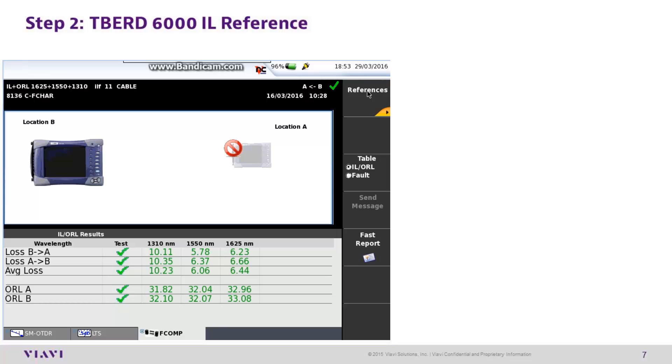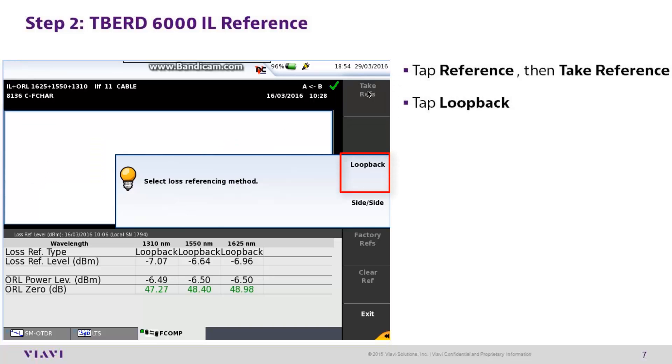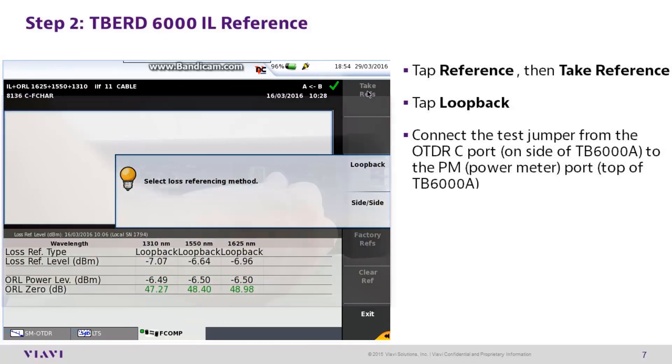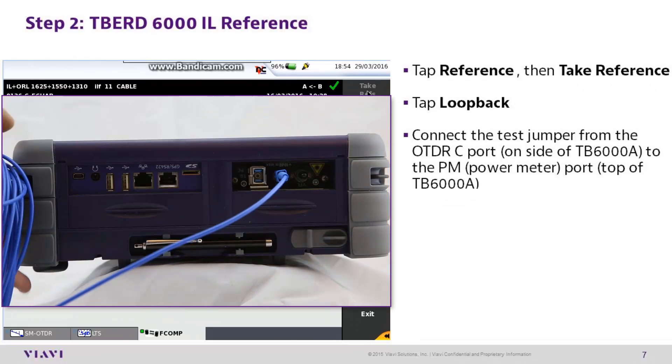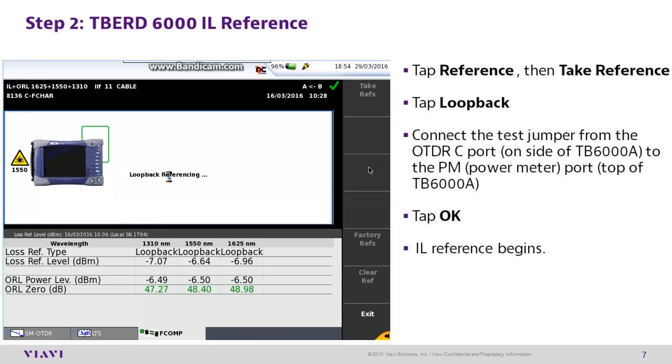TBERD 6000 step 2: performing insertion loss reference. From the fComp results screen, tap reference, then take reference. When prompted, tap loop back. Connect a 30-foot jumper from the OTDR-C port to the power meter port on the mainframe. Tap OK. The insertion loss reference will begin.